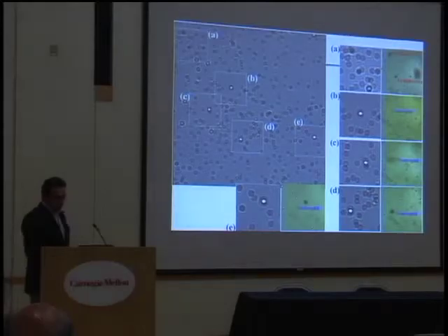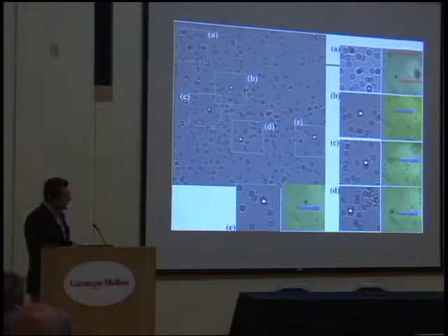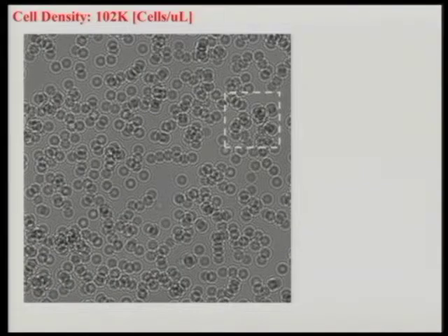And these are some particles that uniquely show the differences between different particle types based on, again, the texture that you get. And if you look at whole blood with the same simple lens-free shadow imager, you'll be seeing shadows of specimen, in this case red blood cells. Every now and then you would be seeing white blood cells with distinct shadows. And that's a starting base for actually something more complicated in the sense that it can be used as a cytometer based on these shadow differences, but it starts to fail as the density of the cells gets higher, as shown here where the cells are clustering.